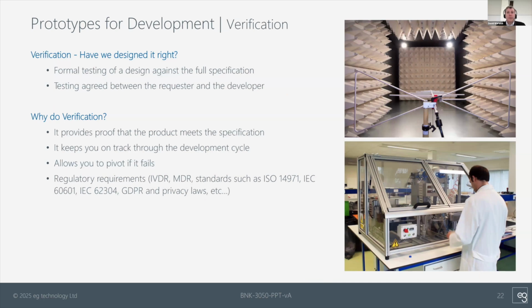Having talked about user needs, specifications and prototypes, one of the main reasons we do all this is to get to the point that you're able to test your device. So when talking about medical device testing, we tend to talk about verification and validation. The medical device regulations are also concerned about these different perspectives on testing. So verification is checking that you've done it right, that the product performs as you set out to in the product requirements. Generally speaking, this is empirical testing. Are the measurements accurate? Are they repeatable? Does the device work consistently and reliably?